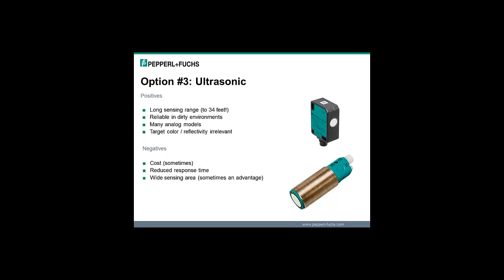The response time for ultrasonics, because they rely on the speed of sound, is a little bit slower. So look at your data sheet to make sure the response time of the ultrasonic you'd be looking at is suitable for an application.